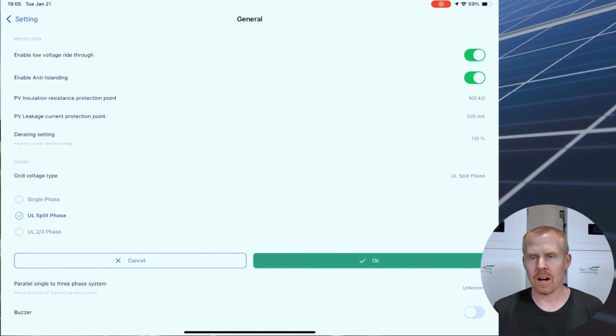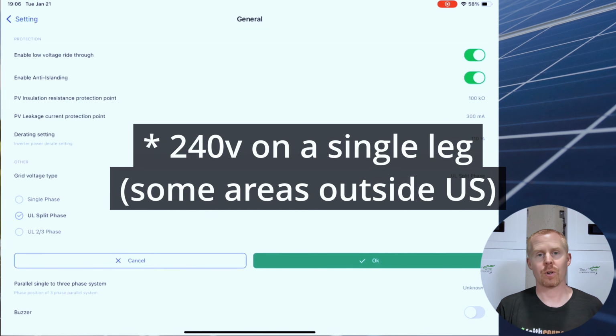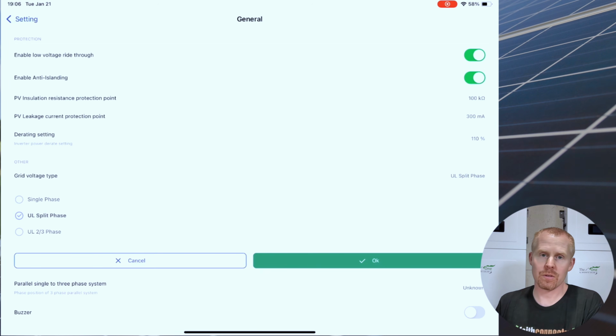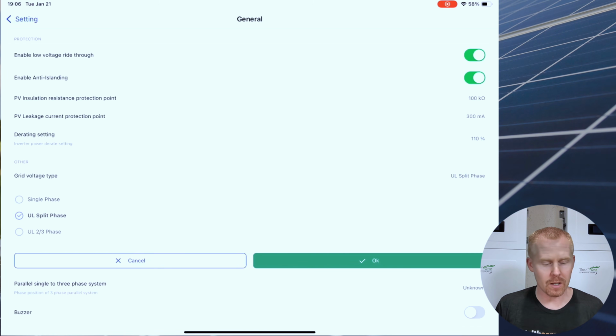Down under other, there's three options. Single phase, which is not a 120 volt single phase, it's a 240 volt single phase, as opposed to 120/240, which is the second option, UL split phase. So if you want your inverters to only utilize 240 volts, then you would have it on single phase. If you're going to use 120/240, then you want UL split phase. And then there's also a UL 2 or 3 phase. Looks like it's for 2 phases of a 3-phase system. I'm not quite sure what that means.